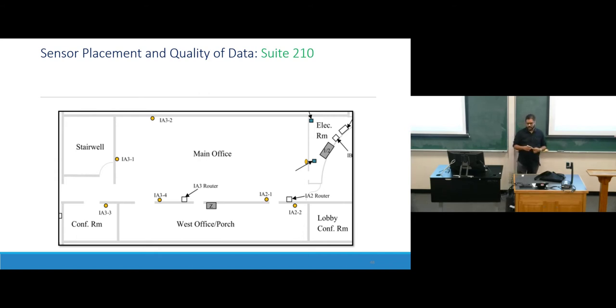That's a meaningful approach. The underlying question is, what is the temperature of a space? You can never actually measure the true temperature of a space, only point measurements. So it becomes important to check whether wherever you've placed the thermocouple or thermostat has any bias compared to, say, the mean of uniformly placed sensors, or you could place sensors based on how the room is used, where most occupants are.